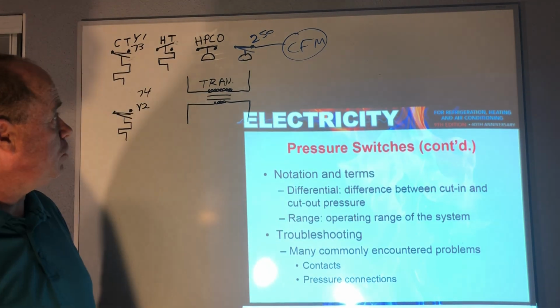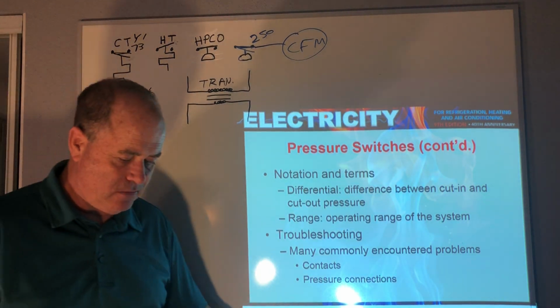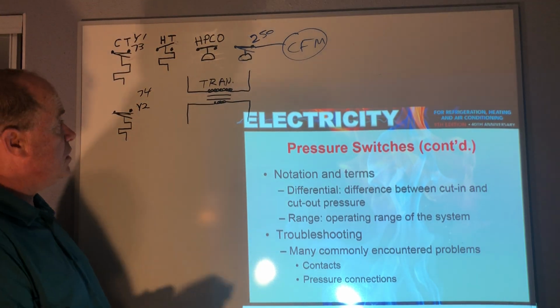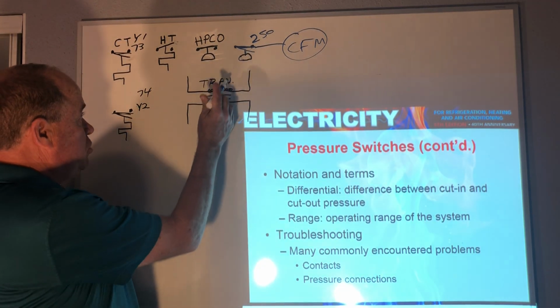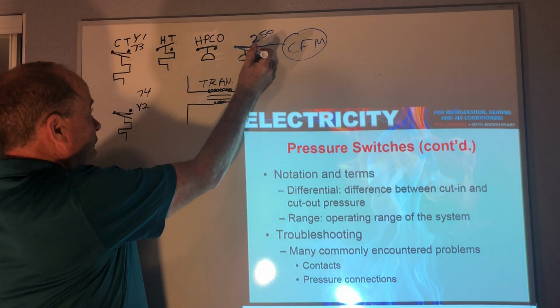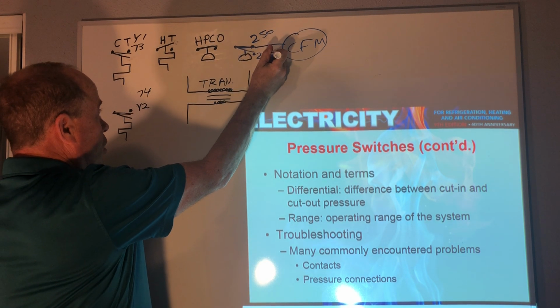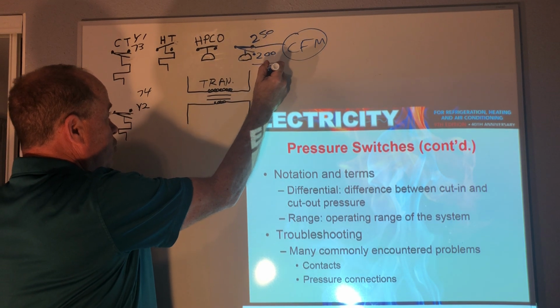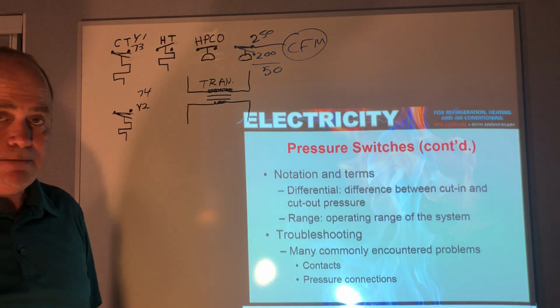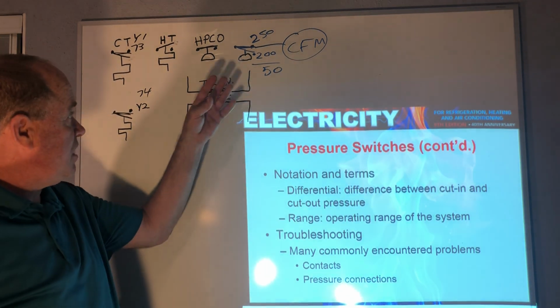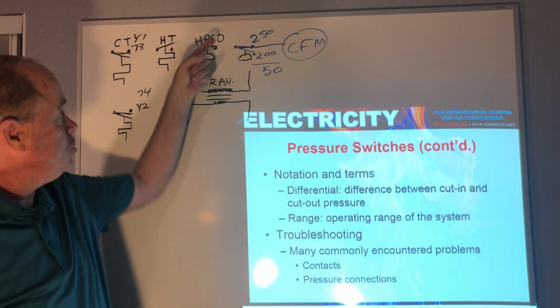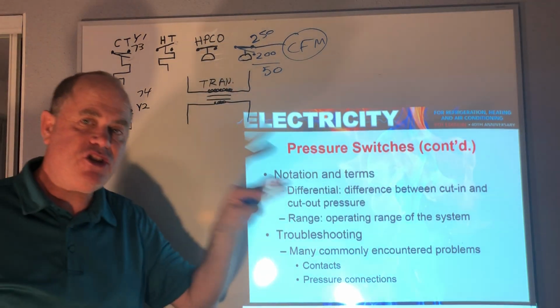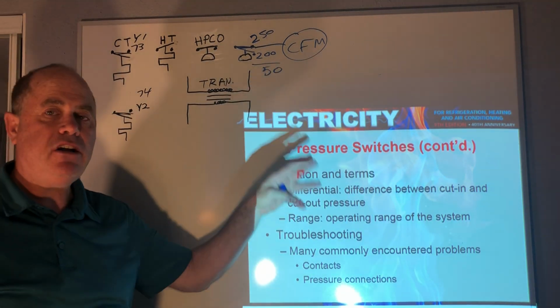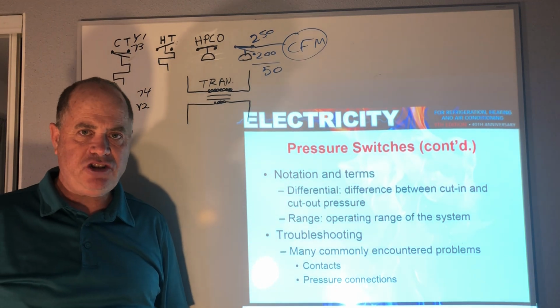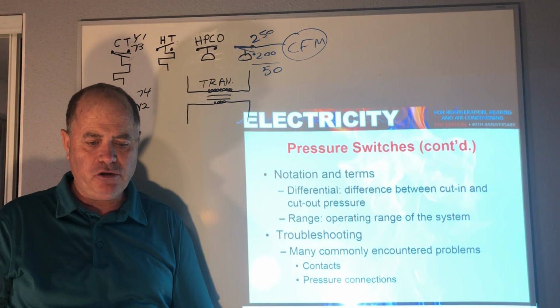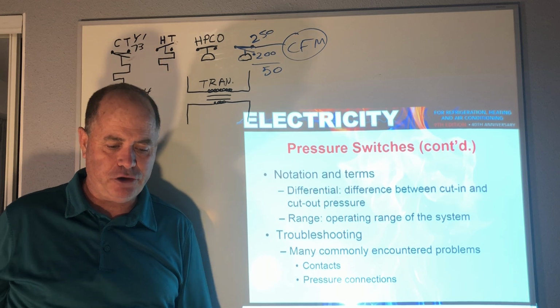Now the differential, let's talk about that for just a minute so you understand. Going back to our illustration, it makes at 250, and if it were to break at 200, we would say the differential is 50 psig. The cut in is 250, the cut out, or when we shut off that fan, is 200, with a 50 psig differential. Those are very common pressure control terms.